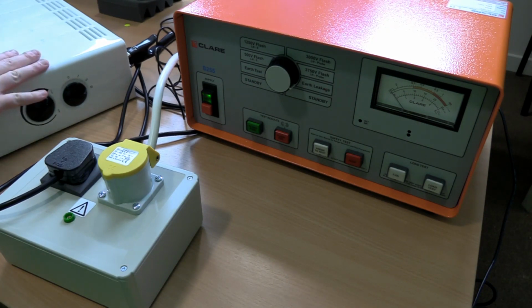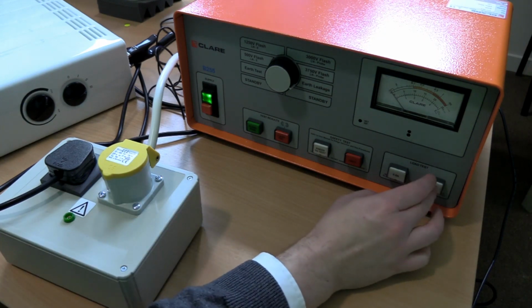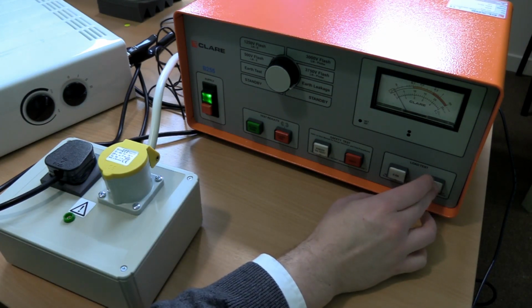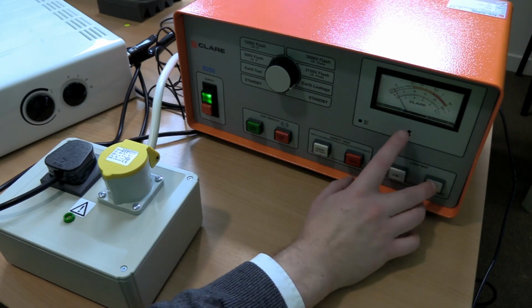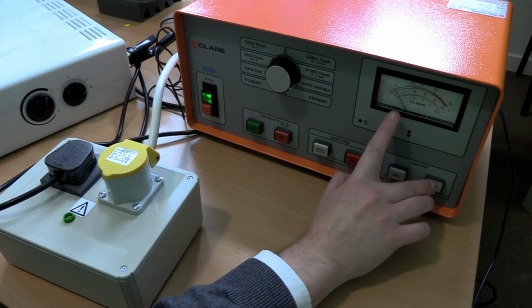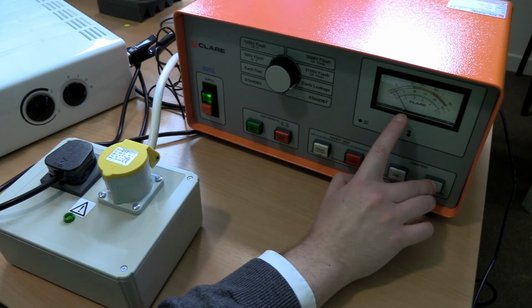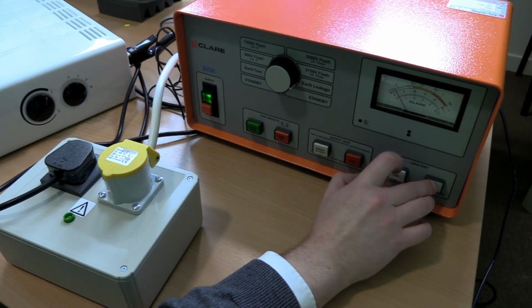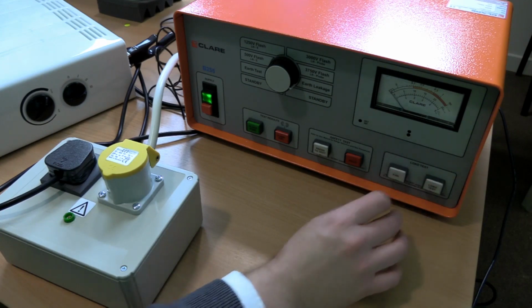I mean, this is a heater that I'm using, so when I power this up, it is going to get hot. Be aware that whatever you've got plugged in is going to heat up. So this time I'm going to hit load test. So I'm now powering up this heater. I can feel it getting warmer. And we're looking for this leakage. This leakage at the bottom is what we're after. And so you can see that we're getting a very low milliamp leakage here, so that's fantastic.